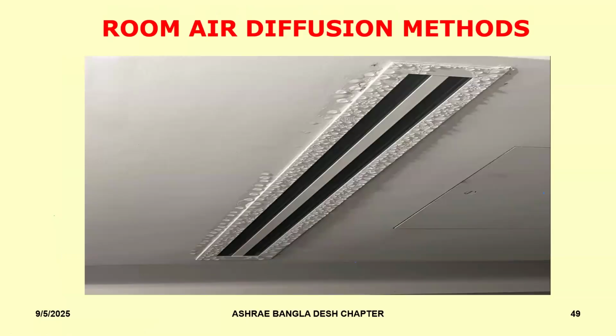Have you seen this? This is something that I actually saw in a hotel lobby at the entrance. There is this outlet on the ceiling right in front, right on top of the reception area. And every time that front door would open, there would be a big gust of warm, humid air that comes in. It hits that outlet, and then you have all this condensation that happens. And very soon over here, you'll see black marks, fungus, and growth that is happening, which is going to contribute to the poor air quality in the space. And then, of course, you have this constant problem of water dripping on the table or on the floor. Somebody has to be constantly cleaning it. So these are things that you need to be very careful about, to make sure that there is no ingress of outside hot, humid air into the conditioned space where your outlets are located.